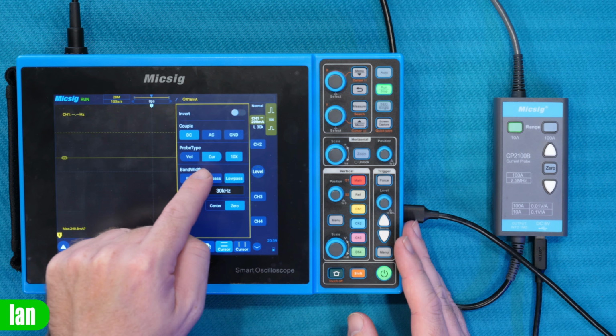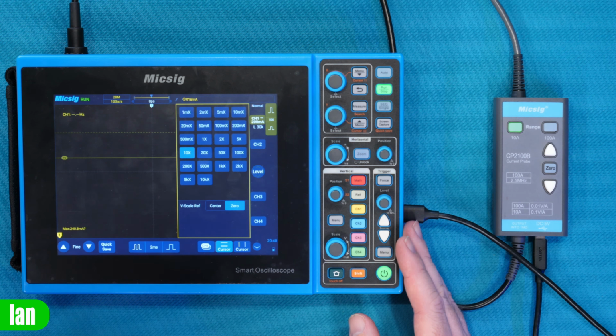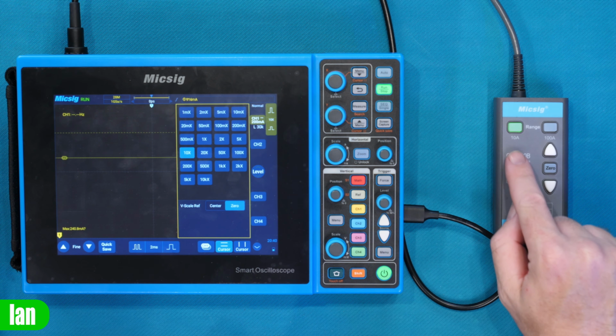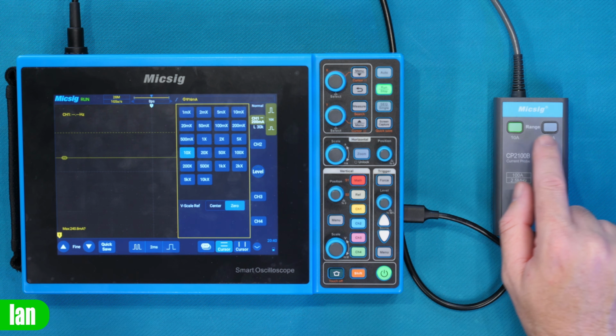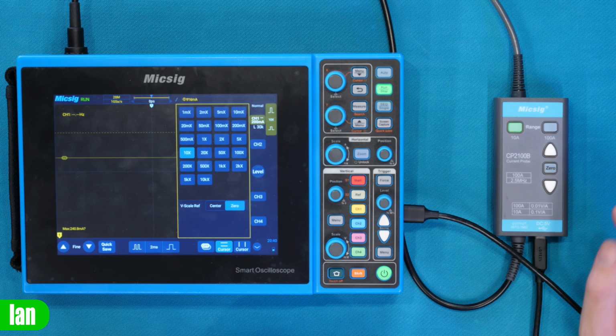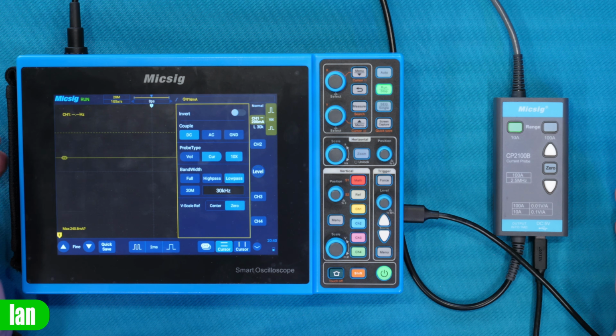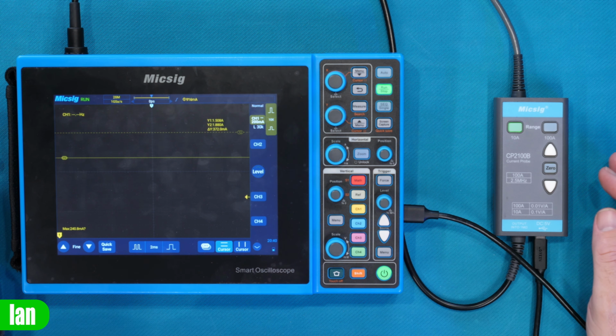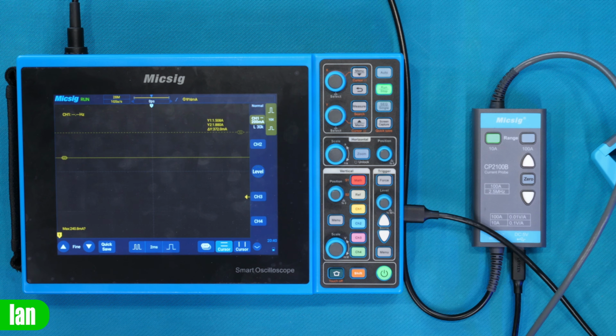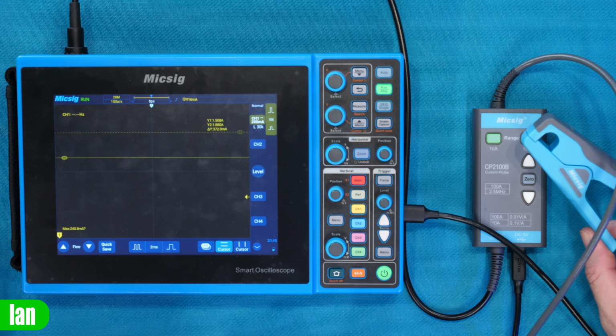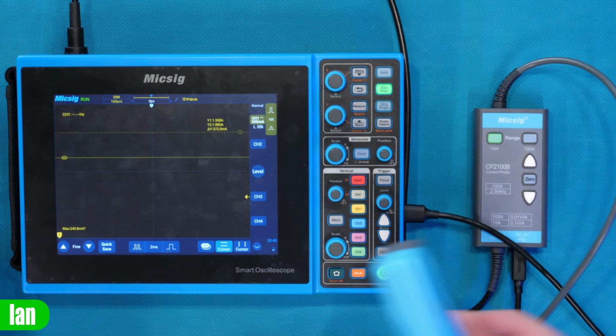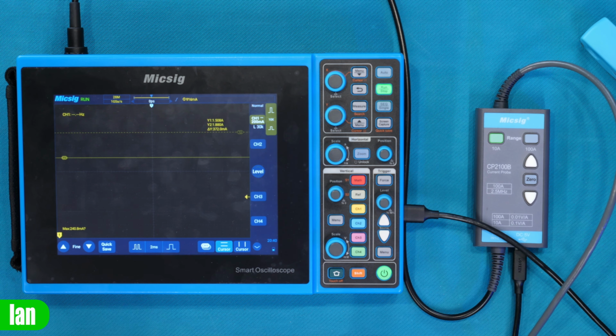And then we need to make sure that we have the setting here, which is the ×1 ×10, the input settings correct as well. On this probe, if you have it on 10 amp, you need it on ×10. And if you're going to use it on 100 amp, you would use it on ×100. So it's very easy to do, but you do need to make sure that you do get that right before using it. Now that we've got it set up, we've got the probe correctly aligned, what we can then do is do the calibration. Now, as I've said, you need to calibrate the probe in free air before using it on whatever device you want to be measuring. So what I'm going to do is simply place the probe here on the bench on its own, and we're then going to press the 0 button, and what that will do is take a 0 reading from the probe. It'll beep a few times and then it will be ready to use.